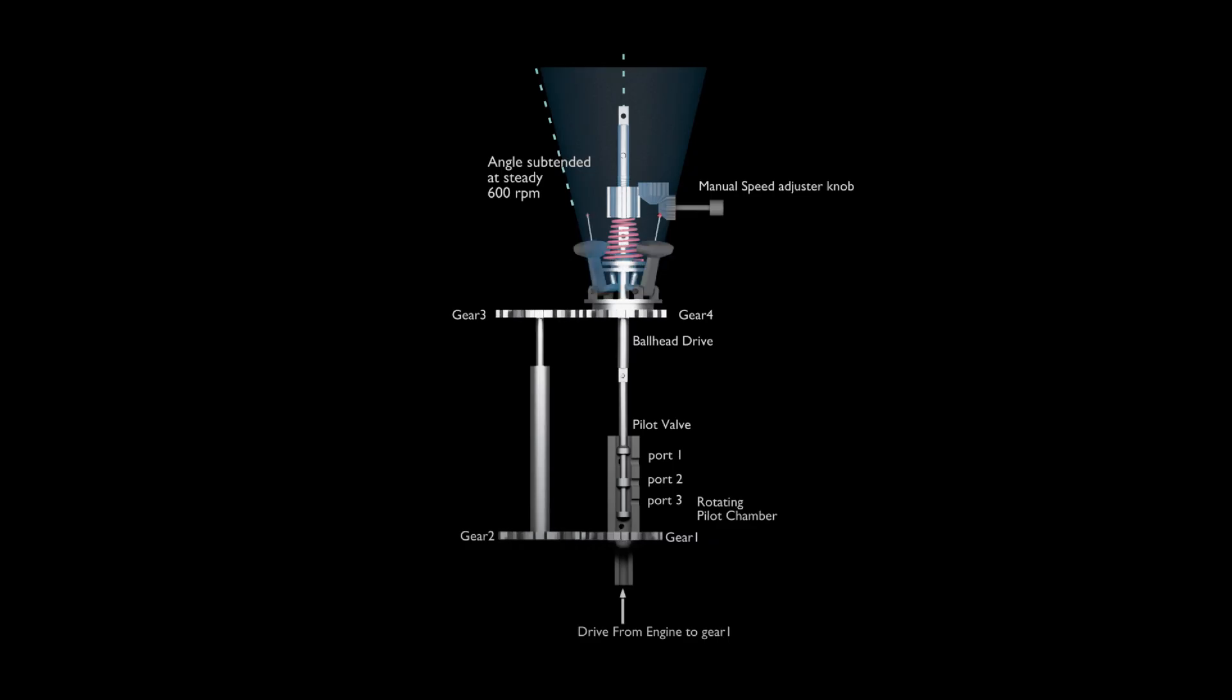As soon as 610 RPM is reached, flyweights move further away from axis, lifts up the pilot valve, this time in opposite direction. Power output shaft of governor moves to lower fuel setting. Again, the cycle of correction starts in opposite direction. This phenomenon is called hunting, hunting about the desired set point.